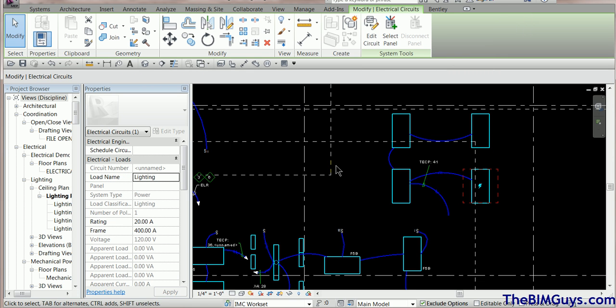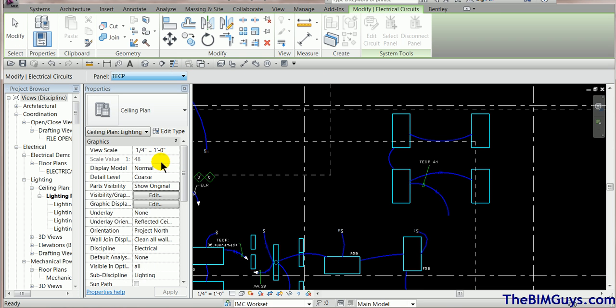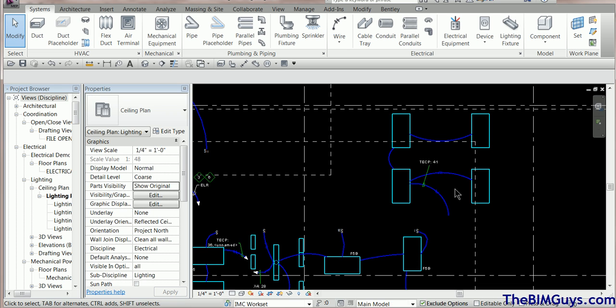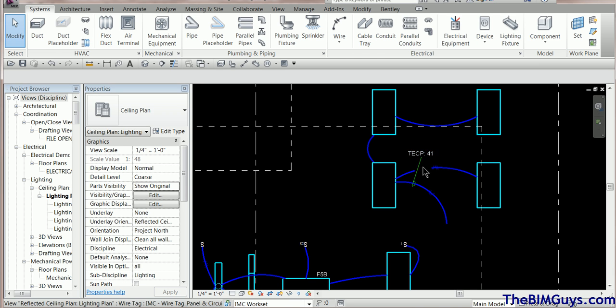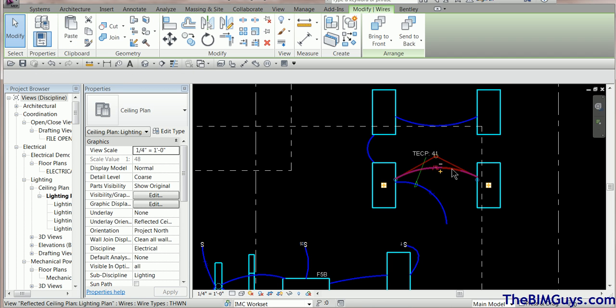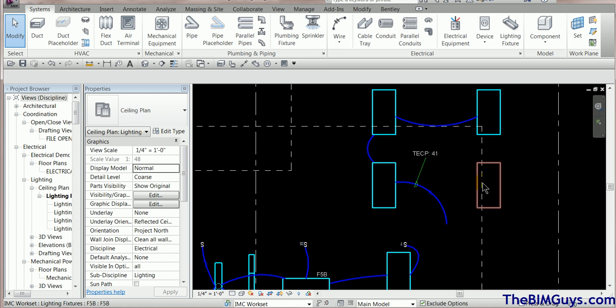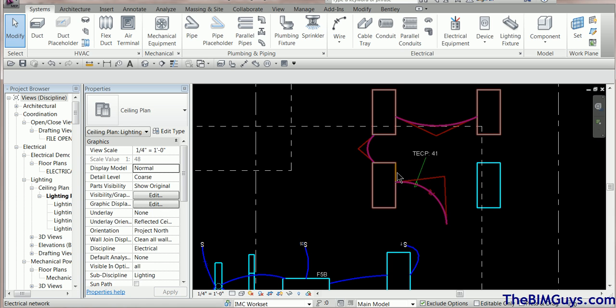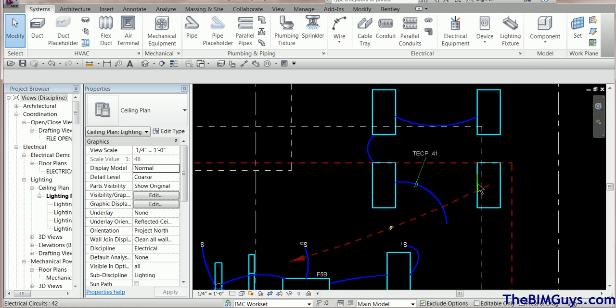We're going to grab this element, power it up, and point it to the same panel. It should go to the next circuit — the last was 41, so this one picks up 42. Now if I grab the tag and move it slightly, it will update. Notice how using the Tab key while hovering over a unit picks up all fixtures as a group, which makes it easy to set up a home run.